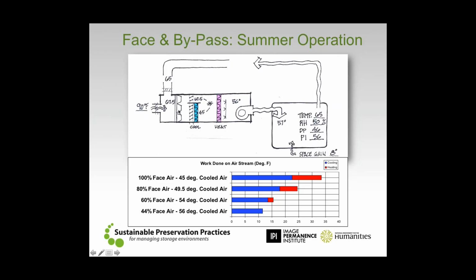So here we are at the cooling coil, and this would be the face route. But the bypass damper, that bypass route, allows us to send some of that air around the coil and go by it and use that air, and here's the key, on the other side of the cooling coil as free reheat. In other words, we warm up this cooled air condition before it ever hits the heating coil. This is a good option in terms of trying to save a little bit of energy here at the heating coil.